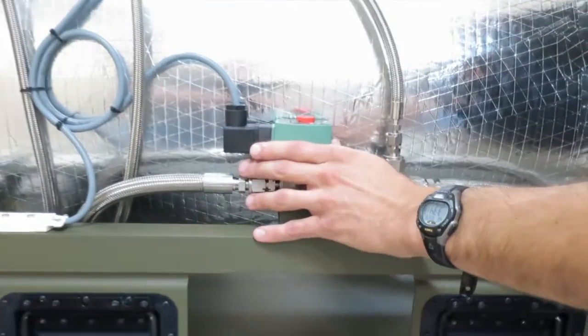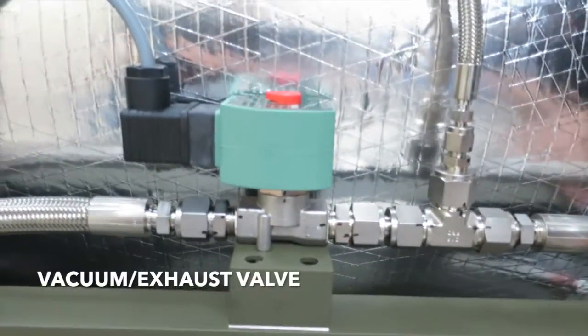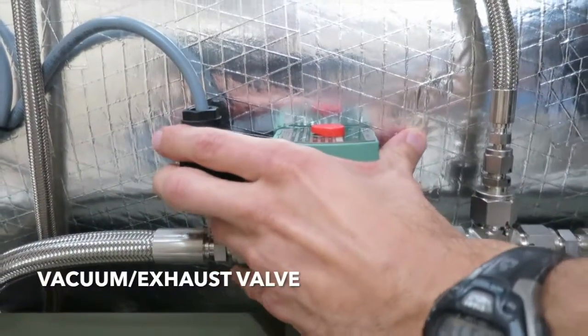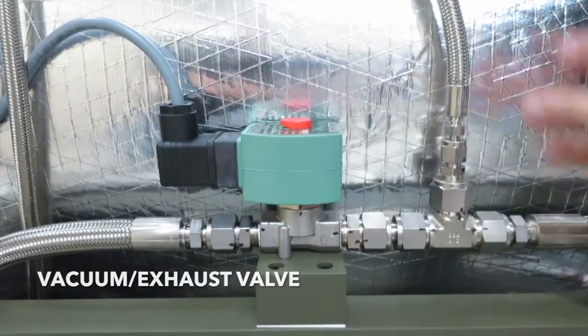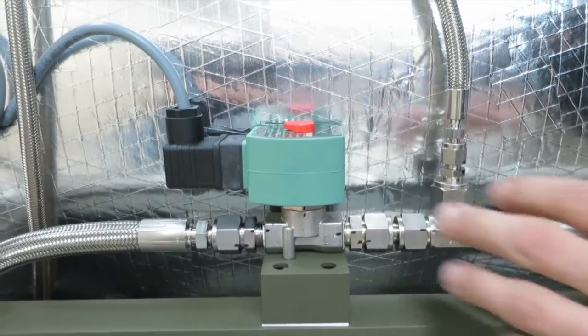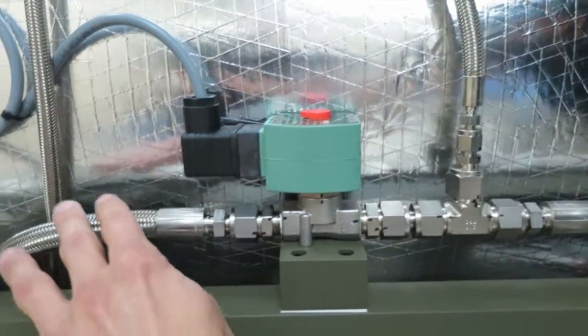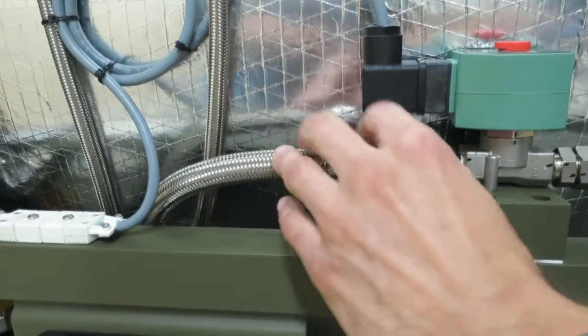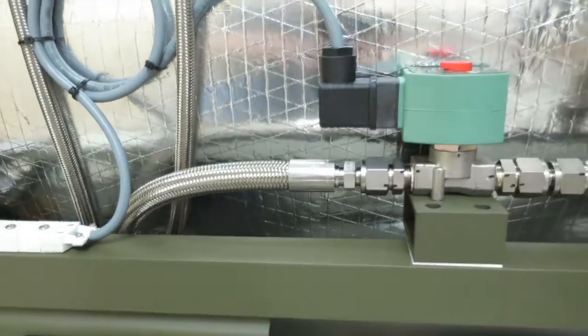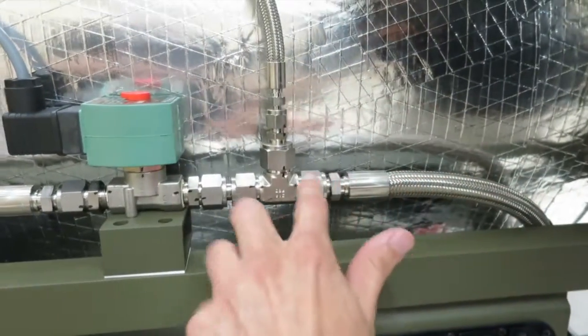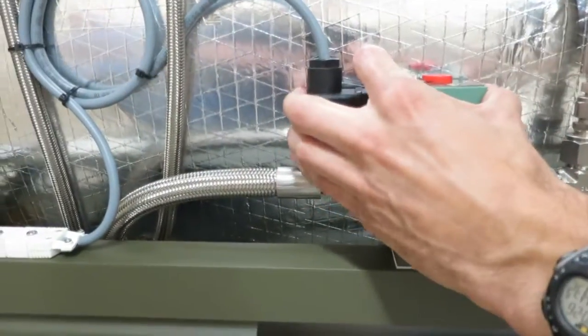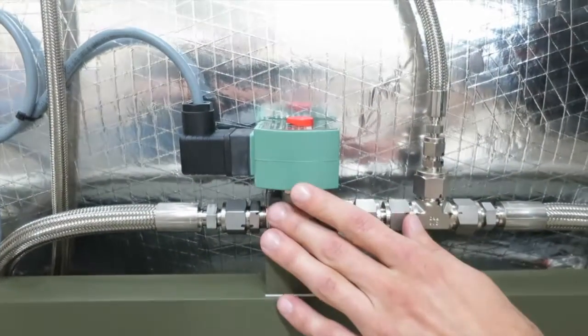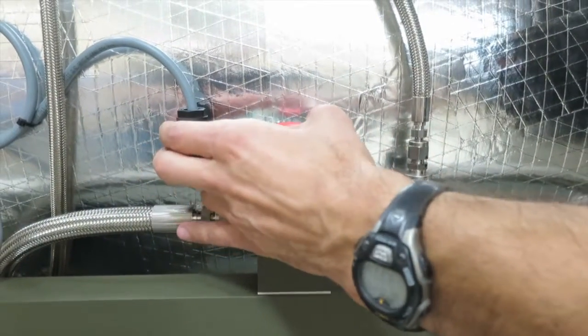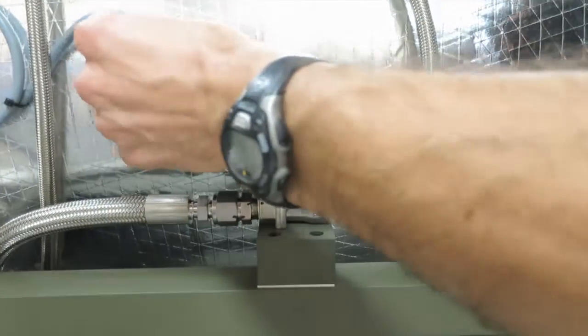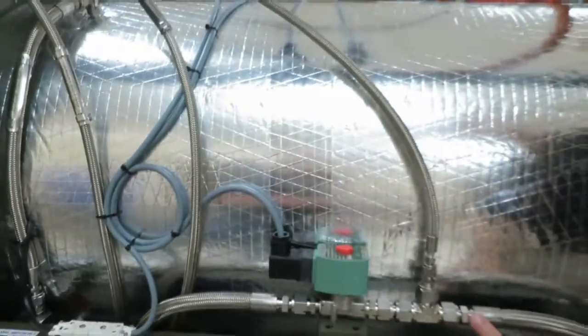Right here we got the vacuum valve. So anytime that the sterilizer evacuates the chamber, pulls out the steam, pulls out the air, this valve opens and the water recovery system pulls a vacuum through this side and all the air and steam is pulled out of the chamber. So this is a solenoid valve, just like all the other ASCO valves throughout the sterilizer. And so power is applied here. This runs back into the electrical enclosure.